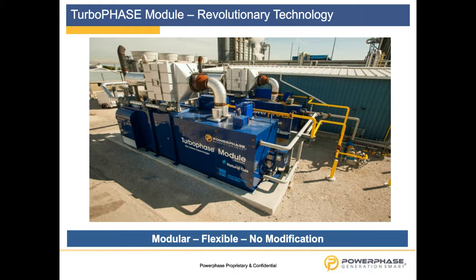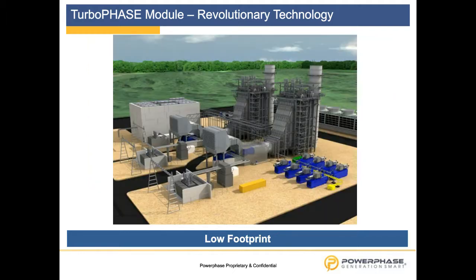The next graphic is showing the real footprint. It's a graphic showing an F-class 2 gas turbine power station, and you see on the right lower side 8 Turbophase modules in real scales, accounting in that particular power station setup for 52 megawatts. And you see the size of this Turbophase system, consisting of 8 Turbophase modules, is small compared to the overall size.